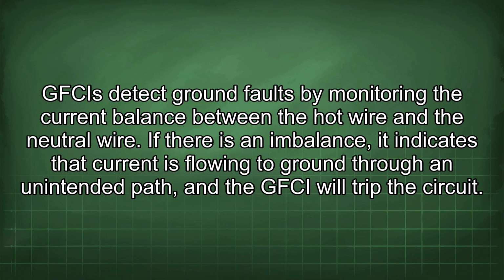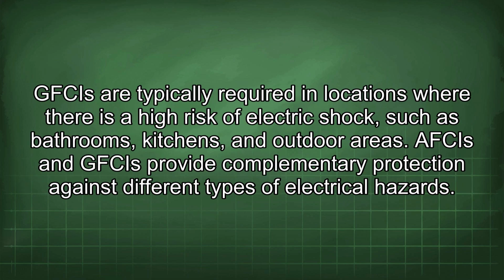GFCIs detect ground faults by monitoring the current balance between the hot wire and the neutral wire. If there is an imbalance, it indicates that current is flowing to ground through an unintended path, and the GFCI will trip the circuit. GFCIs are typically required in locations where there is a high risk of electric shock, such as bathrooms, kitchens, and outdoor areas. AFCIs and GFCIs provide complementary protection against different types of electrical hazards.